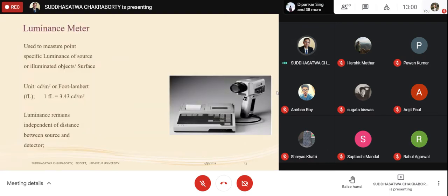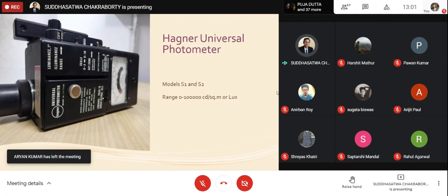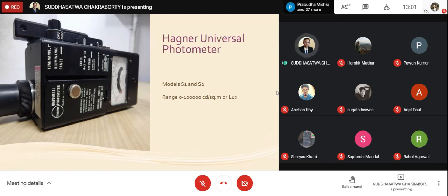For luminance measurement, luminance is the solid-angular flux in a given direction — it represents how much light is coming towards your eye. Dedicated sensors are used to measure luminance in a given direction. The Hagner universal photometer is a very interesting piece of equipment — as the name suggests, this dedicated photometer can measure both illuminance and luminance. We have an analog version that I believe was bought around 1985.